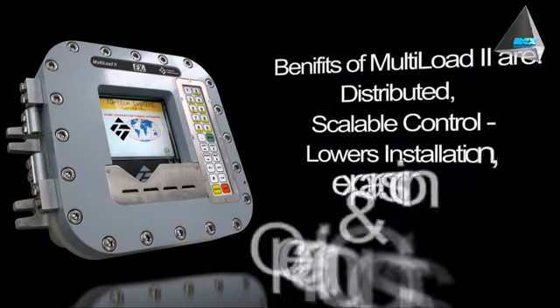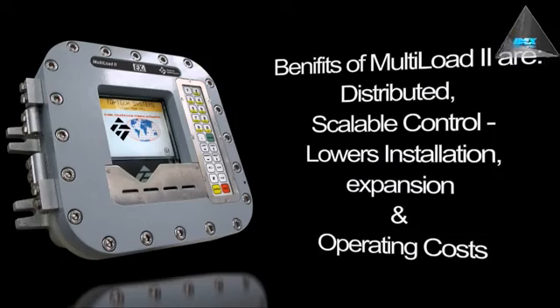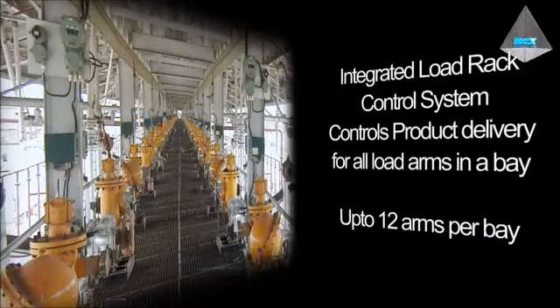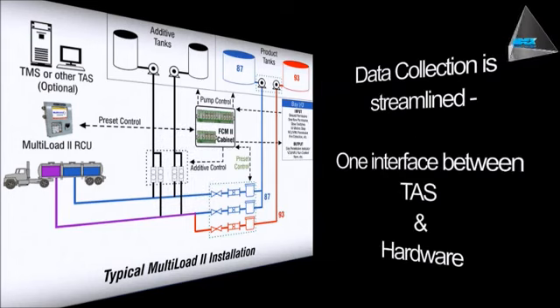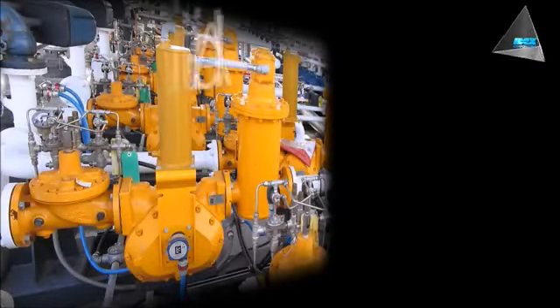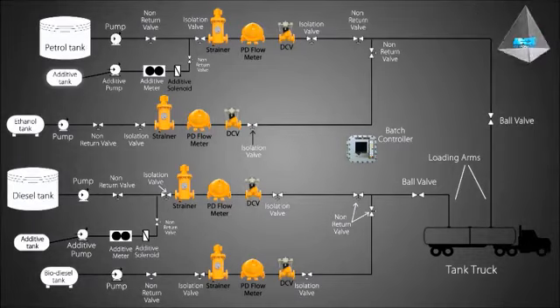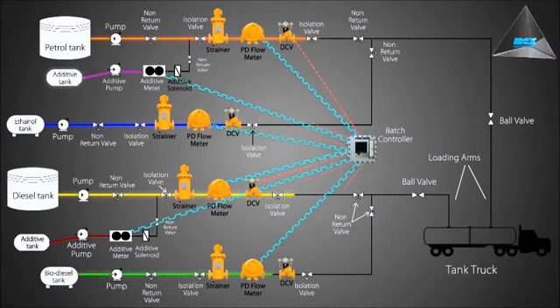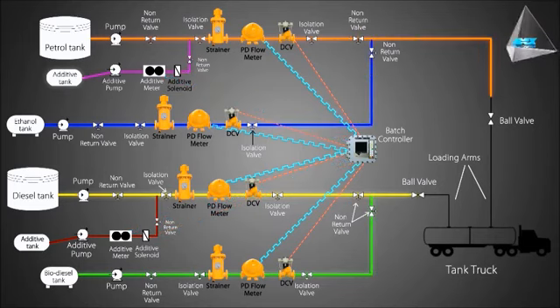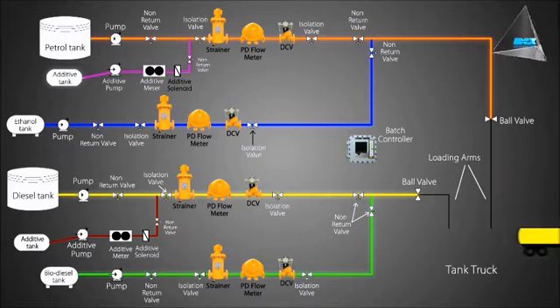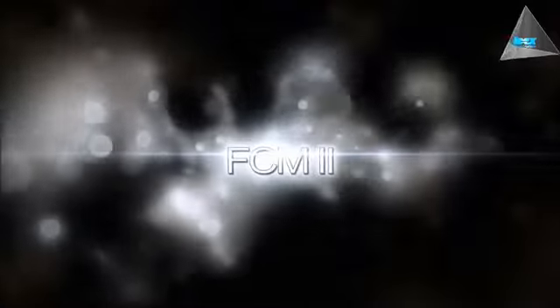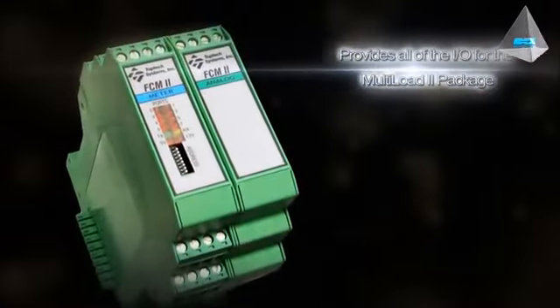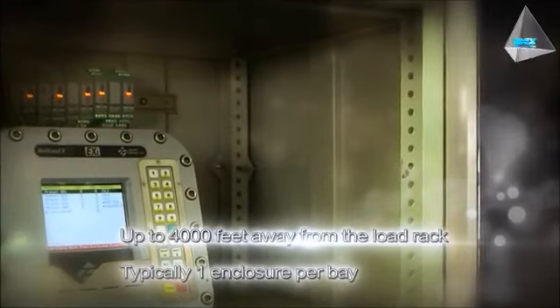The benefits of Multi-Load 2 are distributed scalable control, which lowers installation, expansion and operating costs. Data collection is streamlined, with one interface between TAS and hardware. Same hardware and firmware for all control devices simplifies installation and maintenance and lowers cost of ownership. Flow Control Module 2. Flexible input and output for the Multi-Load 2 package, mounted in an enclosure up to 4,000 feet away from the load rack. Typically one enclosure per bay.